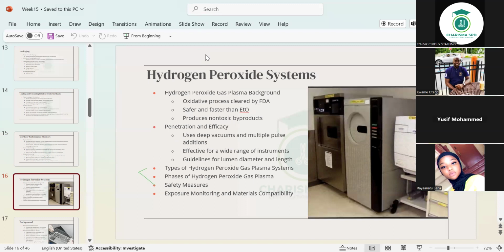We use hydrogen peroxide systems there, where the sterilizing machine has some cartridges, they call them cassettes, that we put in and the machine disperses it within itself. You don't have to do anything else apart from inserting the cassette and then choosing the cycle. Which standard do you want? We have about three different cycles on it: the flex, the standard, and the express, and you just press.